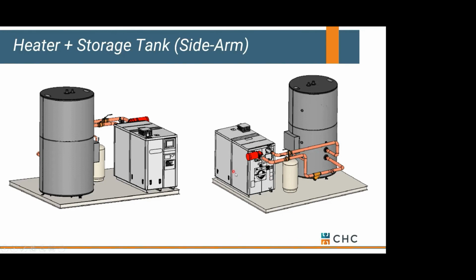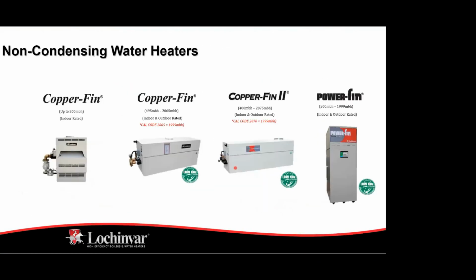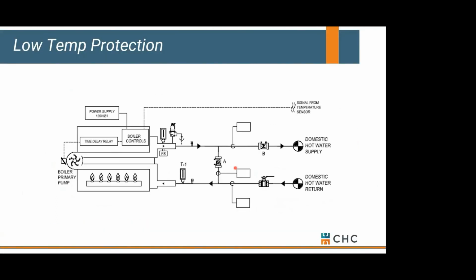But if we decide we're going to use a non-condensing water heater over here, most of the time those have a minimum return of about 130 degrees. So if you're getting 90 to 100 out of the bottom of our storage tank, that creates some real problems for a non-condensing water heater. So how do we deal with that? Because there's certainly both out there. You just need to be prepared for it. How do we deal with a low temperature coming out of a storage tank for a non-condensing water heater?